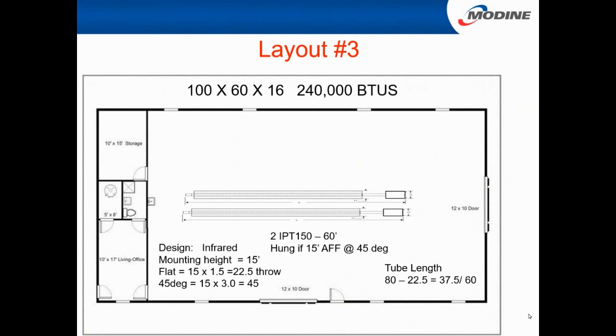So that's where I would put two burner boxes together. That's where you could common vent that if you wanted to. Would I common vent it? No. I like zoning, because that means you're using half the BTUs you really need. And probably most of the time, from probably like 32 on up, one heater is going to heat that building. No problem. Spring and fall, in the wintertime, then, or the guy that does night setback comes in the morning, turns it on, which is really stupid for radiant. What do you do in floor heat? Overshoot. Yeah, you overshoot. So it gets too hot and then you overheat it.